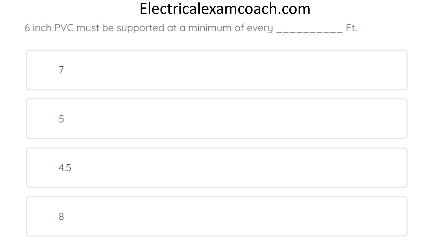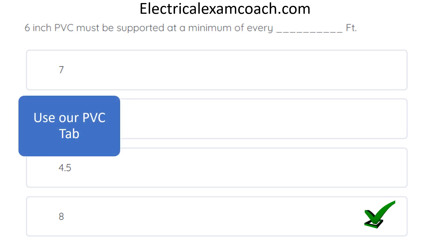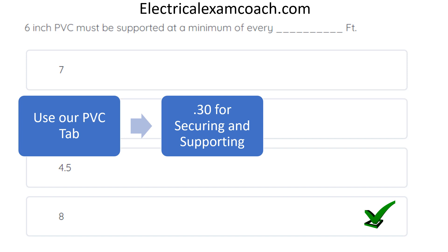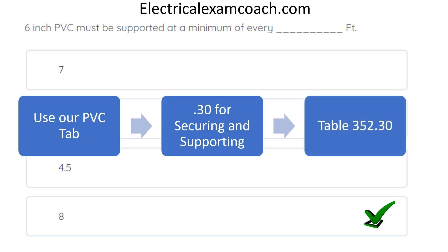Six-inch PVC must be supported at a minimum of every blank feet. The correct answer is 8 feet. We use our PVC tab for this one. For almost every type of cable and conduit, there's a specific article. If you can't tab your codebook, use the keyword and index process. Head to Section 352.30, the securing and supporting section — the .30 section is for securing and supporting across all conduit and cable articles. Use Table 352.30, start on the left-hand side, and select 8 feet.